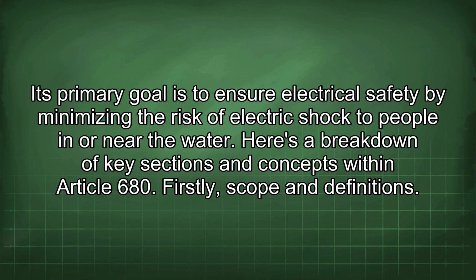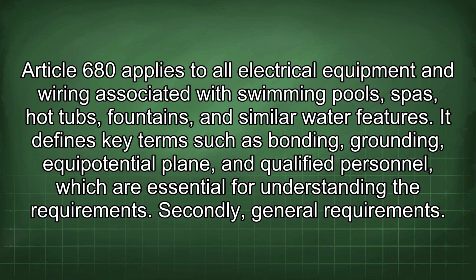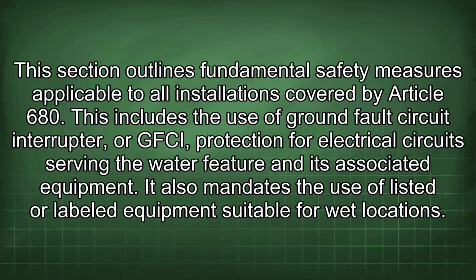Firstly, scope and definitions. Article 680 applies to all electrical equipment and wiring associated with swimming pools, spas, hot tubs, fountains, and similar water features. It defines key terms such as bonding, grounding, equipotential plane, and qualified personnel, which are essential for understanding the requirements. Secondly, general requirements. This section outlines fundamental safety measures applicable to all installations covered by Article 680. This includes the use of ground fault circuit interrupter, or GFCI, protection for electrical circuits serving the water feature and its associated equipment. It also mandates the use of listed or labeled equipment suitable for wet locations.